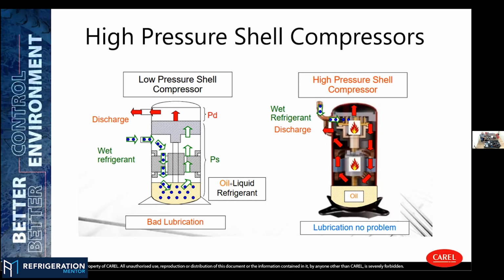Talking about the mechanical construction of the compressor, BLDC technology, and mainly these rotary compressors we are seeing, they have a different logic or a different approach. In traditional compressors, the suction line goes under the compressor. You cool down the motor with this suction gas. It goes to the carter of the compressor, then to the compressor chamber, and then directly to the discharge line. Here you can see it going to the discharge line. This makes you very sensitive to any droplet that could come back from the evaporator. If you have any droplet, it will mix with the oil inside the compressor and wash it out. So you will lose all the oil and start to have mechanical problems inside the compressor.